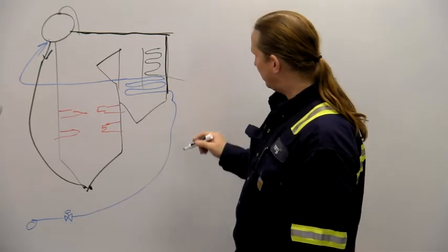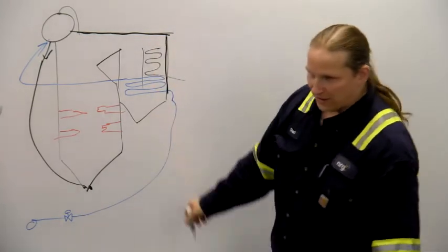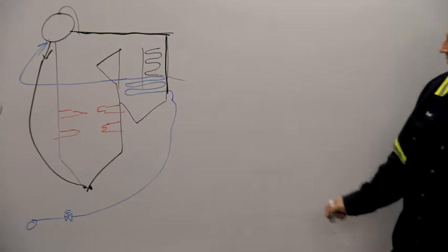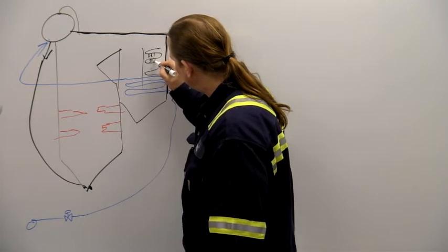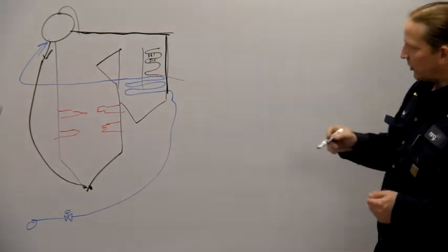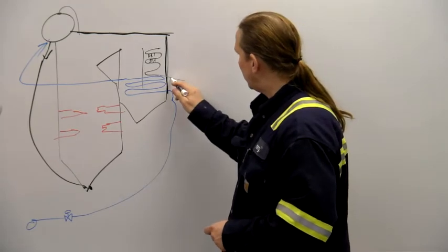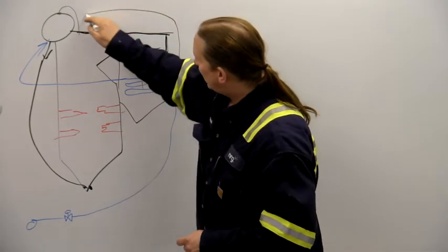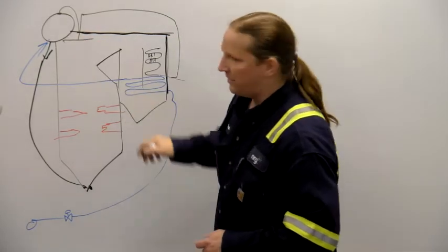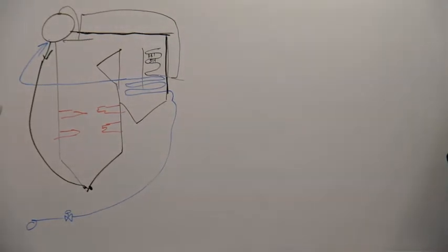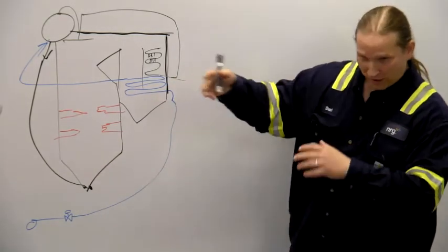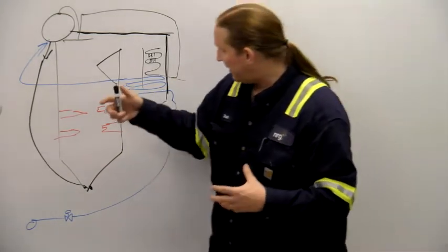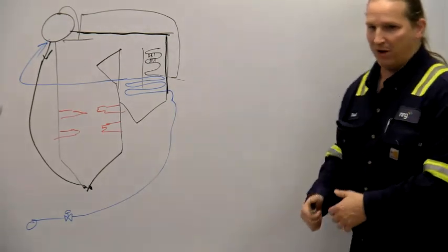And it comes out again. What's this section called? Superheat. Primary superheat. Primary being a fancy word for first. So then that runs back up and goes down here. Hey, what's superheat mean? It means degrees above saturation. Okay, so steam is saturated when it is right at that boiling point or condensing point, and it is superheated when we've added more heat to it above that, when it is above the boiling point.